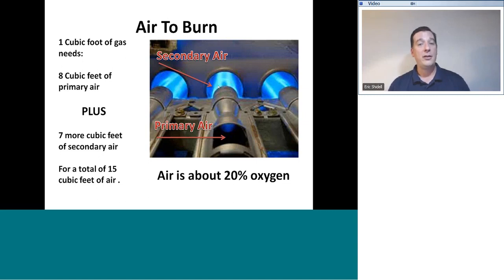When you look at the rating plate on your fuel burning appliance, such as your gas furnace, and it says that that furnace is, say, 100,000 BTU per hour, gas input rating, 100,000 BTU per hour, what that really means is that appliance is designed to consume 100 cubic feet of gas per hour if it runs steadily. If that gas has the appropriate 1,000 BTU per cubic foot, that equals a 100,000 BTU per hour furnace. That's also a 1,500 cubic foot of air per hour furnace.